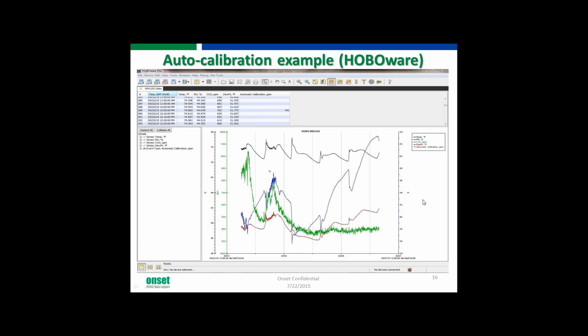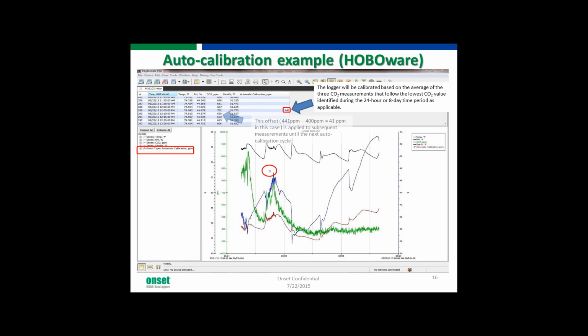This is a screenshot from HOBOware that shows you how an auto calibration event happens, or how it's tagged. Basically what you'll see is over here in the event, it'll say there's been an automatic calibration. It tags it or flags it in the data set. And what this number means is that it looked at the average of the three measurements that followed the lowest CO2 measurement over that 24-hour or 8-day period, and then it calculates what the offset should be from 400, and it applies that offset to your data.